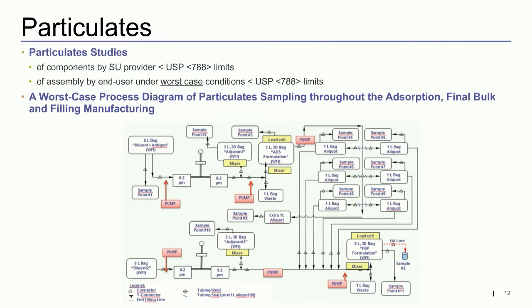This contains the ingredient containers, filters, sterile connectors, welds, and processing lines, all worst case. And what I did was I put WFI, or water for injection, and drew it through the lines, collecting at various sample points. At those sample points, I sent them off to the lab where we could measure by light obscuration in accordance with USP 36, Chapter 788 for final bulk formulations with nominal volumes of greater than 100.